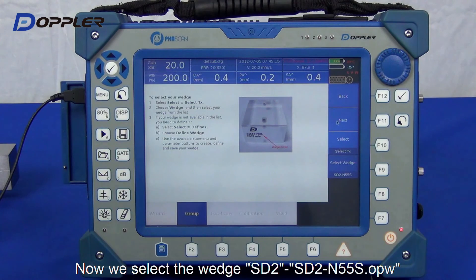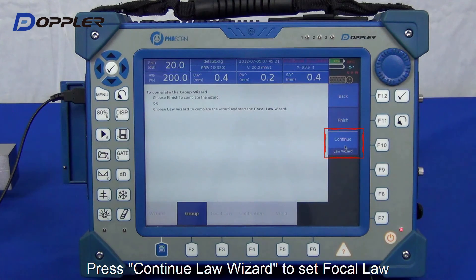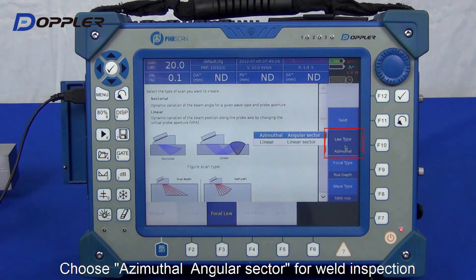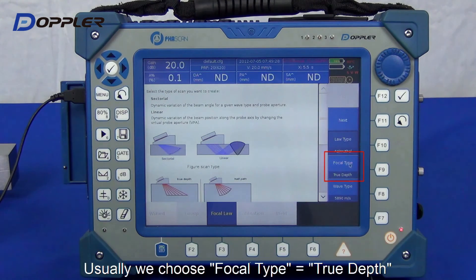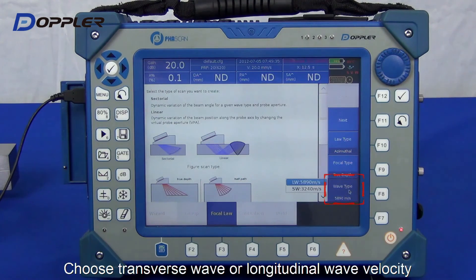Next, wedge selection. We use the default setting here — nothing's changed. And go on to the focal law setting. To perform a calibration, we select a sector scan, true depth, and shear wave.